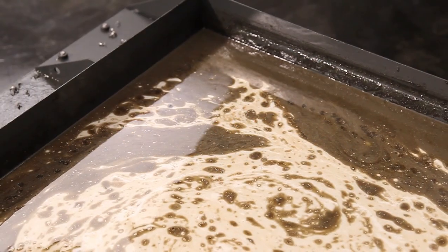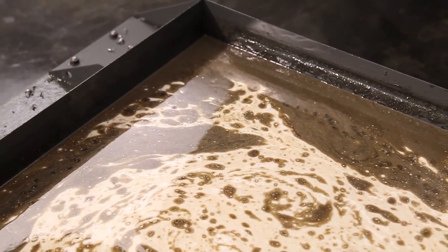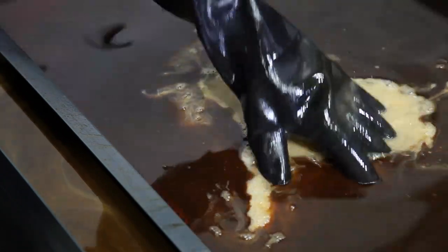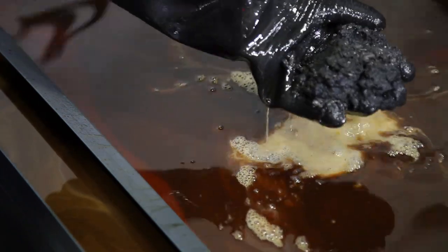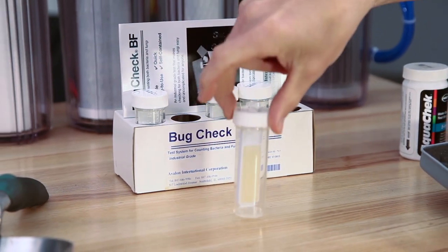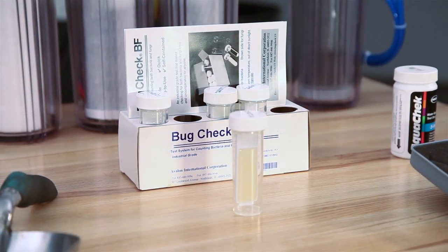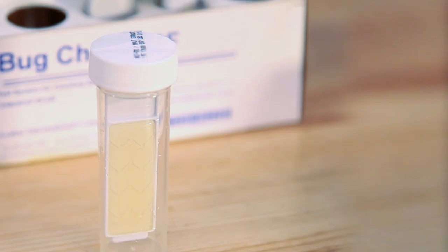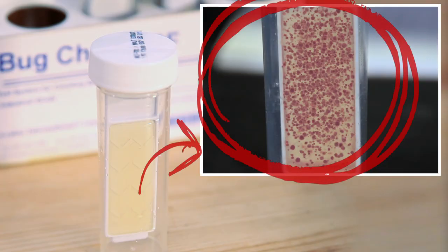However, in the unfortunate event that you've let your tank maintenance falter, you may find it turning into a stinky, disgusting mess. At this point, you may need to test for bacteria in your tank. Here, we're using a bug check bacteria test kit. Take a sample of the coolant and allow it to sit over the weekend. On Monday morning, if it looks like this, you definitely have a bacterial infection.